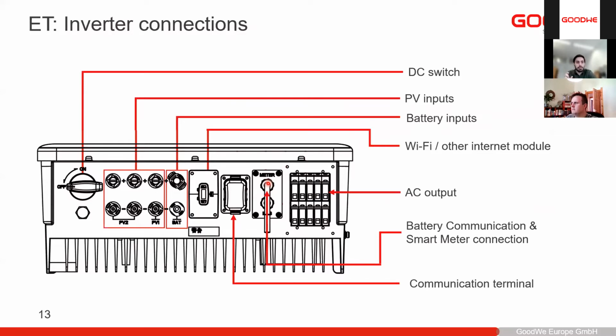And then the current clamps, you need to clamp on the correct phase. It says on the current clamp which phase it should go to. It also has a specific direction. It's very important that you put the CT clamps facing towards the grid. There's a little arrow on the CT clamp, and that will show you in which direction the grid is. Make sure that you're always connected. Also on the side of the smart meter, you can see the proper wiring and which CTs should go to which phase. In case you ever wonder or you lose the manual, it's also located on the side of the inverter. Also, the voltage sense is on the bottom side, and you also need to connect this on the same side as the CTs.